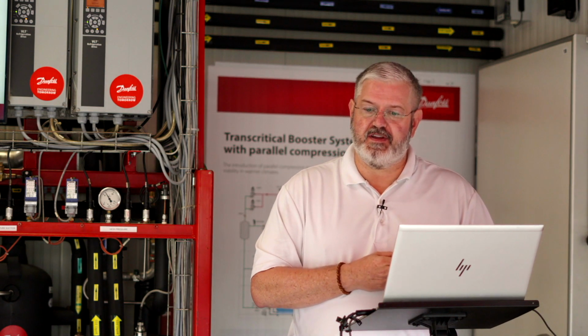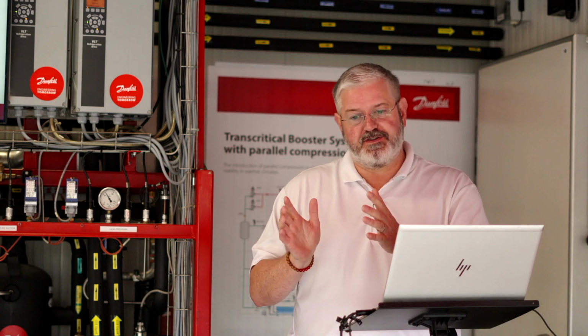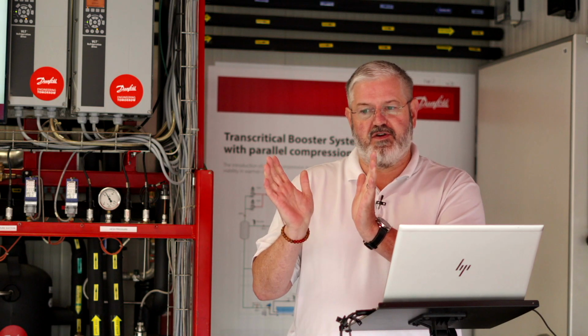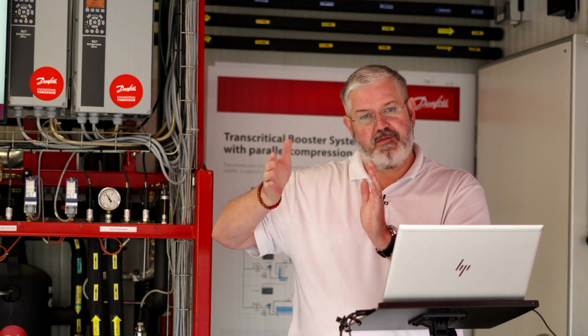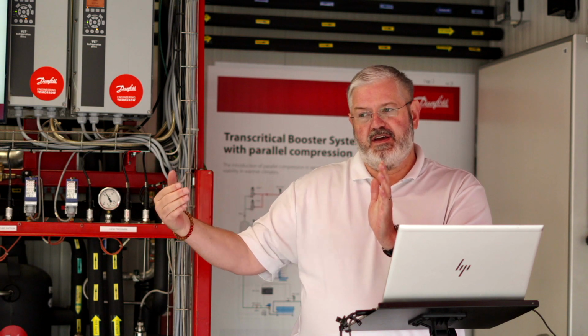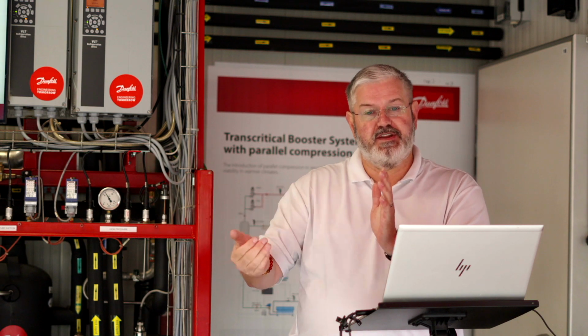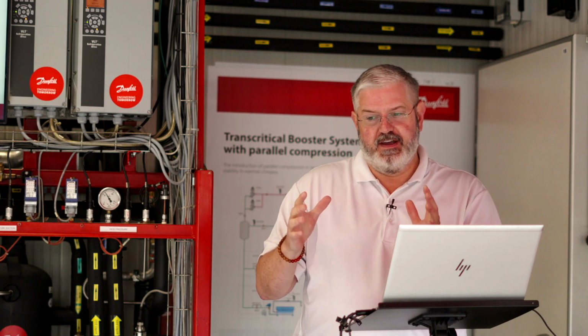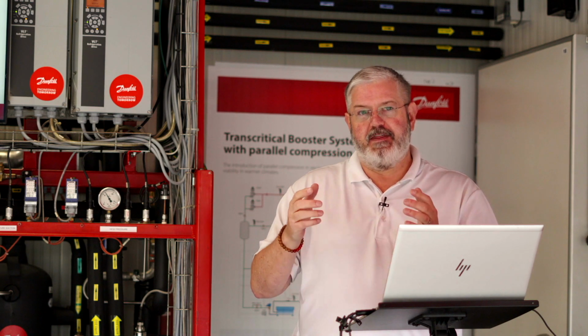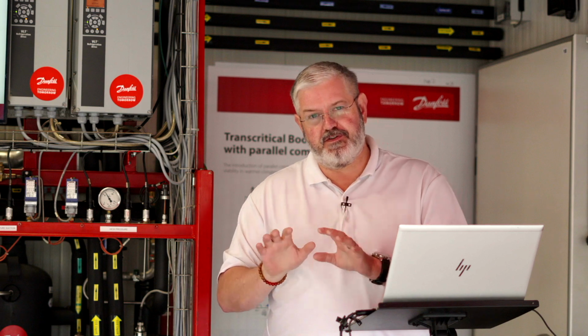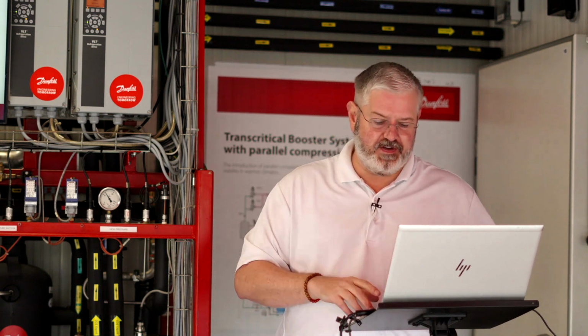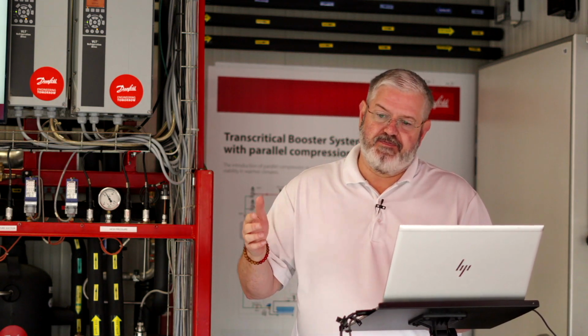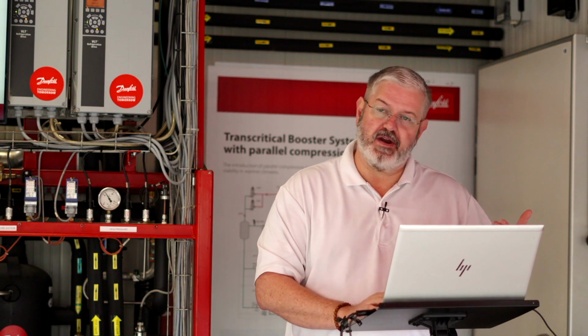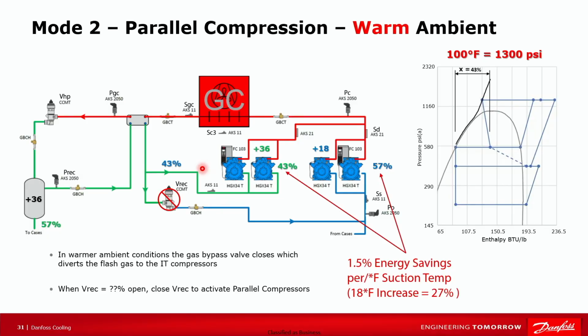And that's basically, if you're not familiar, it's a condenser coil. It's typically a V coil, and it's vertical, and they'll put a pad that they run water across to basically cool the air that the condenser sees, and it kind of lowers your condensing pressure. And that would let you push a transcritical system further south in warmer ambience and still run efficiently. To get even further south, they came up with parallel compression. It was a really smart idea.